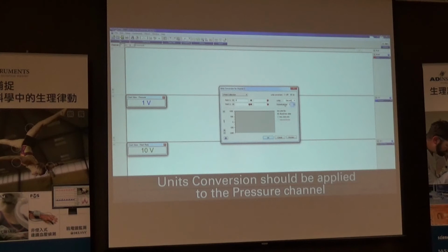Units conversion should be applied to give 0 volts equal to 0 millimeters of mercury, and 1 volt equal to 300 millimeters of mercury. So this is how we actually calibrate the system, because these systems will record everything in volts or millivolts. So we need to tell them the correct unit. If it is pressure, we have to say mmHg is the correct unit.